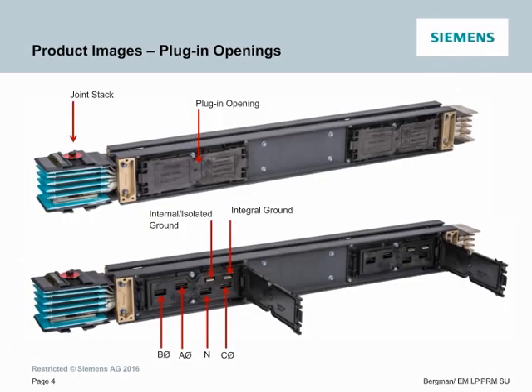On this slide, we want to look at a visual representation of the plug-in openings. As you can see on the first illustration on the top, you have the joint stack, and then you have a diagram of the plug-in opening. Below, you have the multiple phases, the neutral, your internal isolated ground, and then your integral ground that we mentioned earlier. Remember that there are no welds in the conductors or housing ground. All electrical conductors are one piece, which is very important.